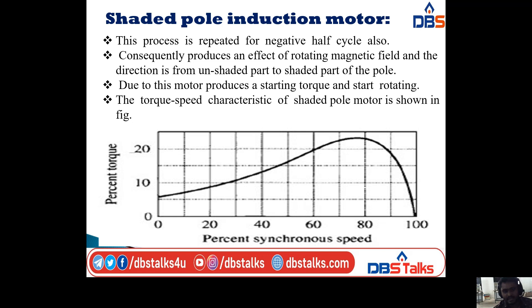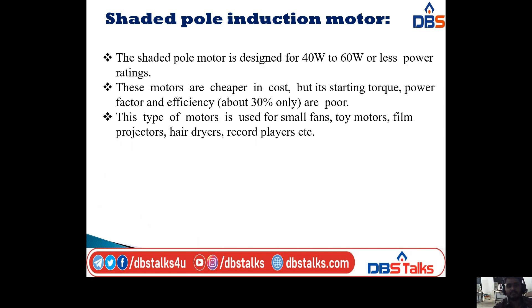This entire process is repeated for the negative half cycle also. Consequently, it produces an effect of a rotating magnetic field, and the direction is from the unshaded part to the shaded part of the pole, causing the motor to produce a starting torque and start rotating. The shaded pole motor is designed for 40 watts to 60 watts or less power ratings. These motors are cheaper in cost.